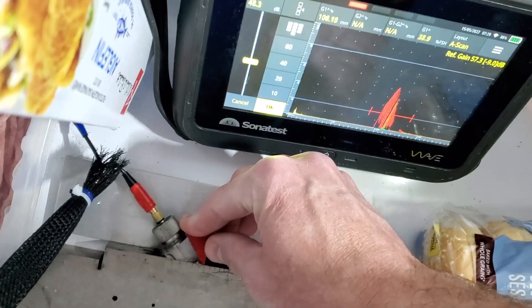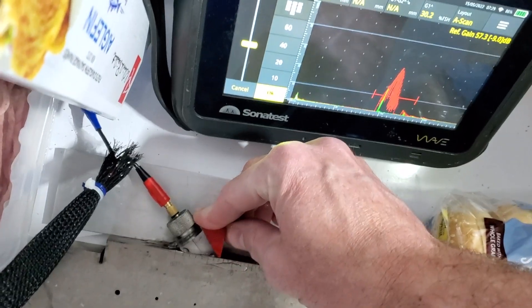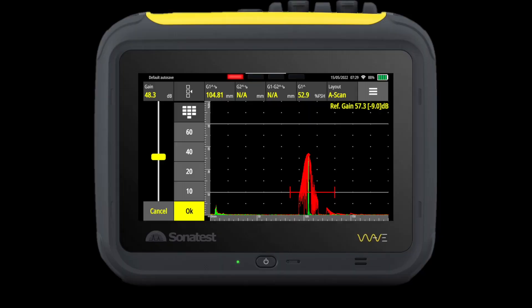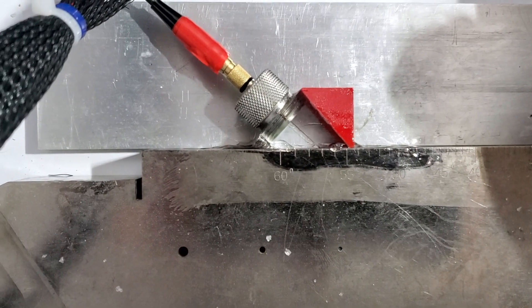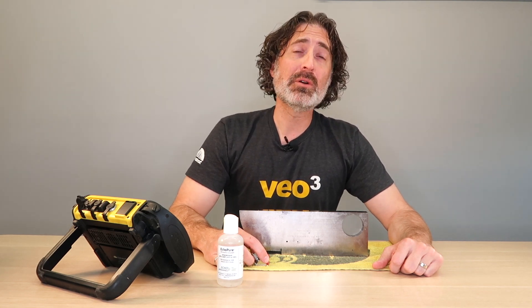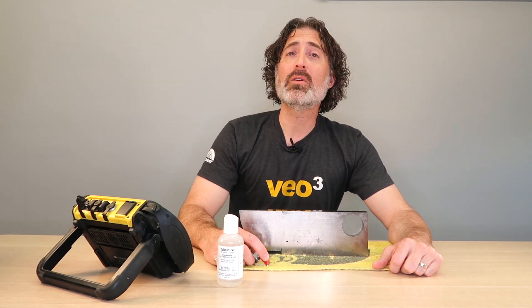Then we took the calibration block and the probe and put it in the deep freezer right next to the hash browns, getting the temperature down to about minus 20 degrees Celsius. Again, we check the refracted angle — moving it back and forth, hitting that big hole in the IIW block — and we peak out at about 57 degrees. So we just saw: as temperature goes up, so does the angle, and as temperature goes down, the angle goes down.